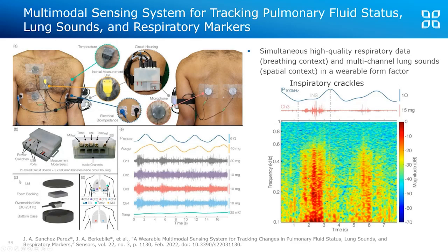If you look at the bottom left of this slide, the amount of work that went into building the casing for the quote unquote microphones, really contact accelerometers that were picking up the lung sounds, was quite extensive, to make sure that the sounds were not being altered by the hardware itself, and to minimize the artifacts from body motion on top of the microphones.